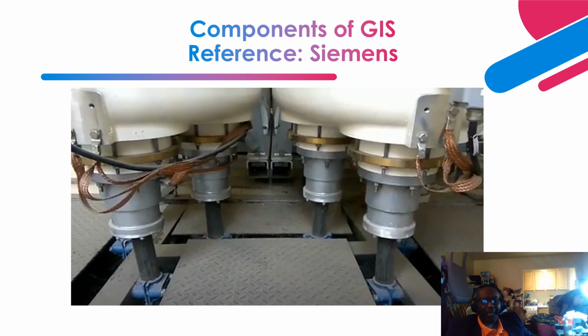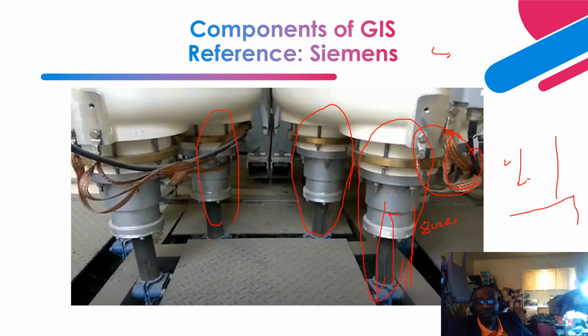Next is the line side, right? Okay, so the line side basically has cables that have been installed in these compartments, and as you can see over here, this is what they call cable sheaths, right? Okay, so you have a cable that is rated for, let's say, 2000 amps. That's the line side cable, right? As part of the cable configuration, we have a cable sheath. So nominal current basically goes through the conductor of the cable during normal operation, right? But when there's a fault, then this is the path for the fault current. Because this one has a very low resistance path for the fault current to flow to ground and to the substation grid. This is bonded to the equipment, and from there, it goes to the substation ground mat, right?